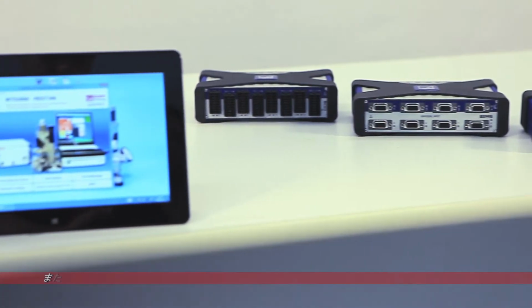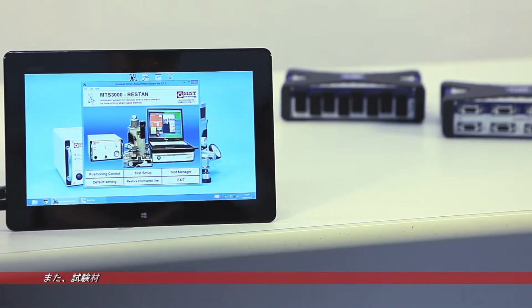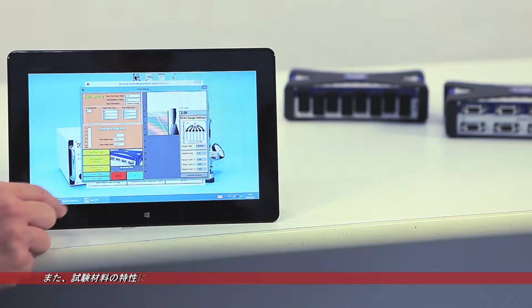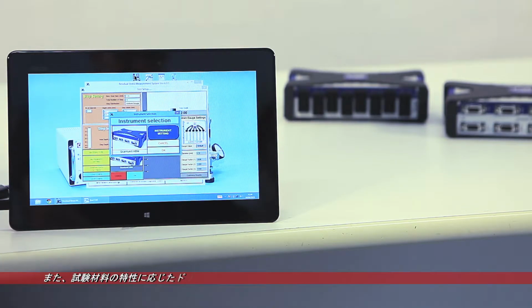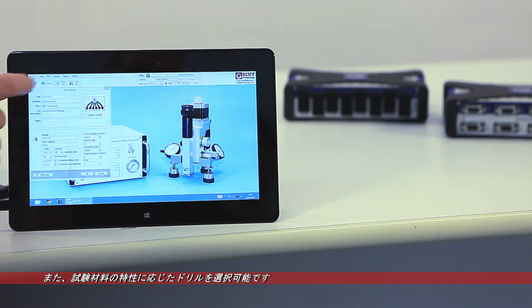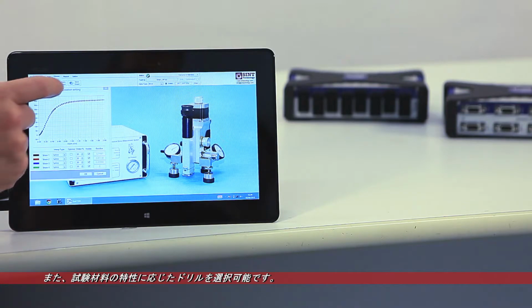For the strain values acquisition, a digital amplifier is used, and a dedicated software allows the full test setup and the back calculation of the residual stresses starting from the measured strain.